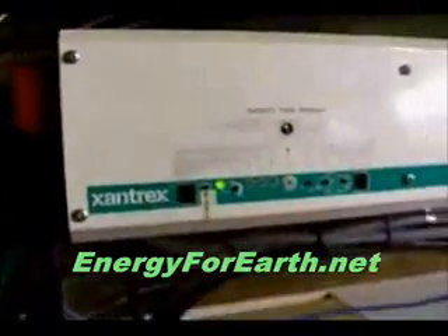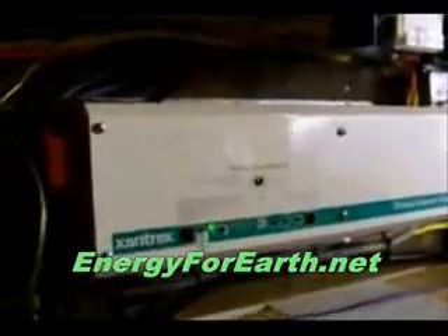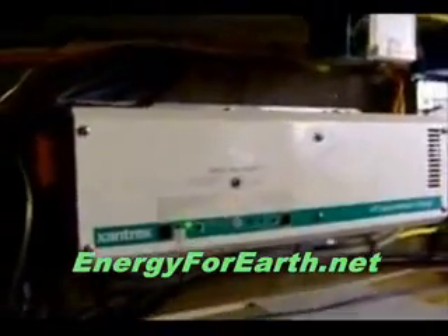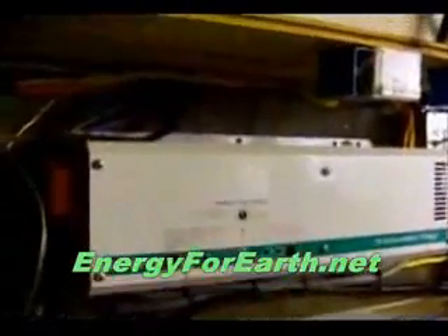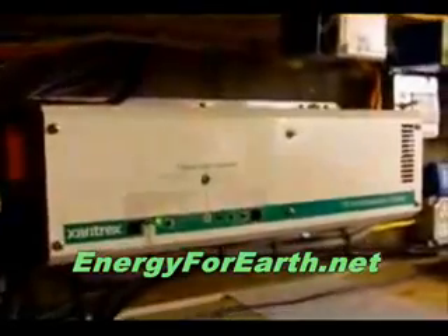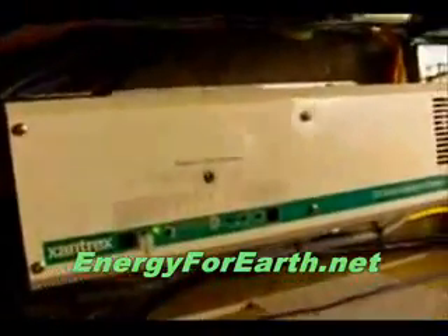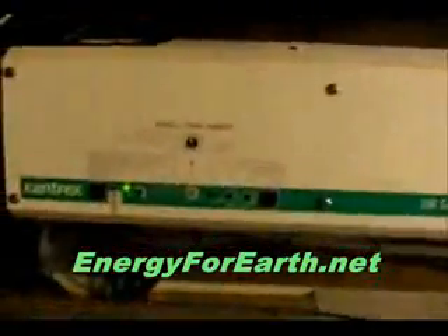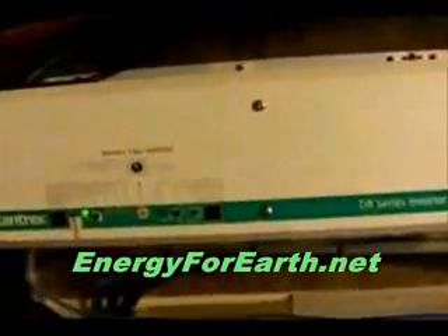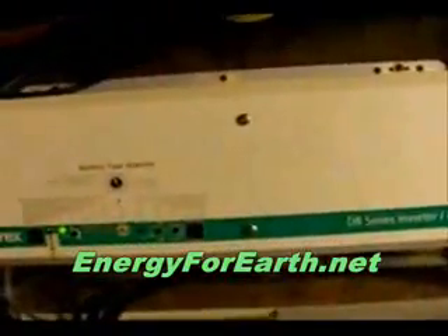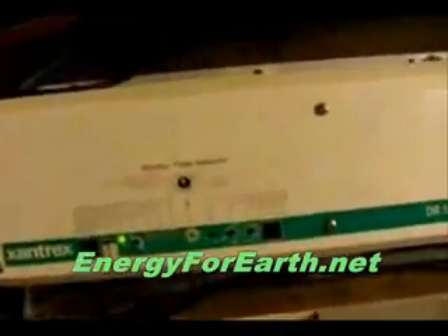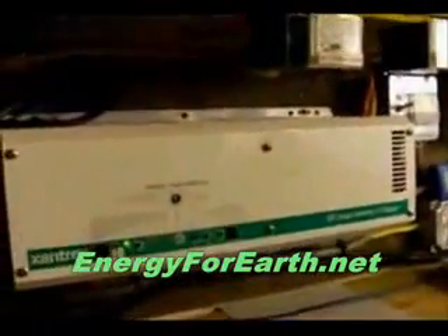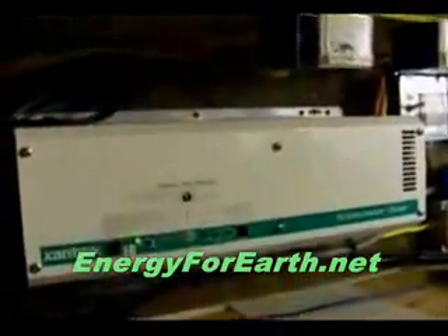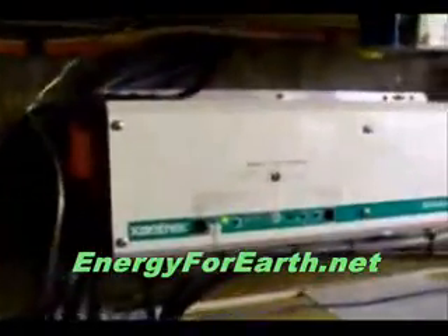Search mode is very nice for a small system like ours, because if nothing is on in the house, no lights, no load present to the inverter, it will enter a search mode. It sends out small pulses of power looking for something to do, and if it finds nothing, it sits there in that search mode forever, taking up a tenth of an amp, 100 milliamps. But if it's running without any load on it, it takes up to an amp or better. So this saves a lot of energy during the day when nothing's on and nobody's home.